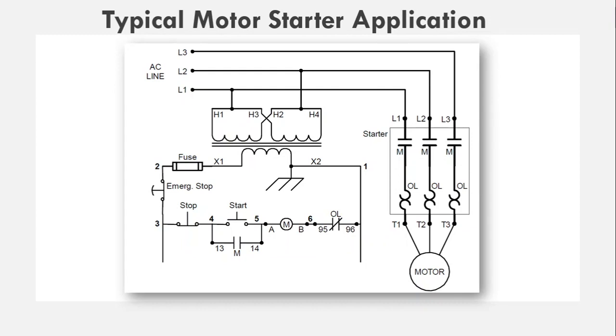In operation, when the rails are powered, pressing the start switch provides power to the motor start coil M, and when the starter actuates, auxiliary contact M closes, which bypasses the start switch. At that point, the start switch no longer needs to be pressed in order to keep the motor running.